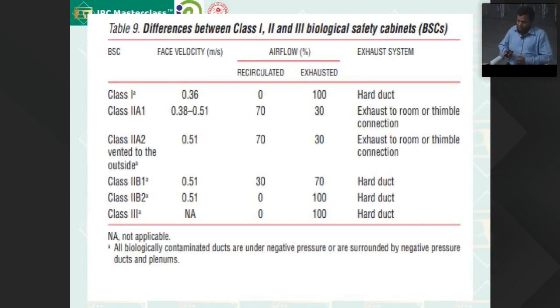This is the difference between the different cabinets in class 1, class 2, class 3. If you see the class 1, 100% exhaust is there and it is connected to the hard duct. Class A1 has 70% recirculated, 30% exhaust. Again, it is exhausted to the room. Same room, if the exhausted air is coming back to the lab, it has to pass through the HEPA filters, or it can be connected outside. In class A, the air circulation requirement is almost the same, but the velocity with which the air enters the cabinet is 0.38 to 0.51, whereas in class A2 it is 0.51. Otherwise, most of the things are similar.